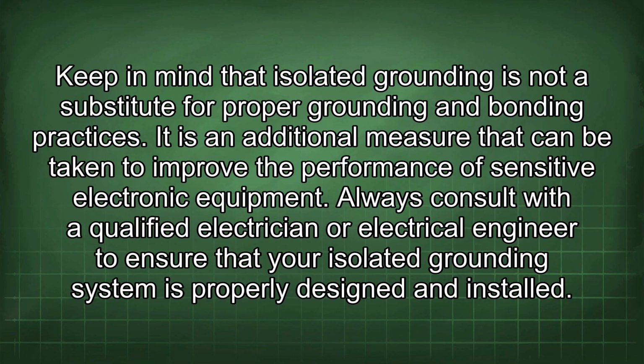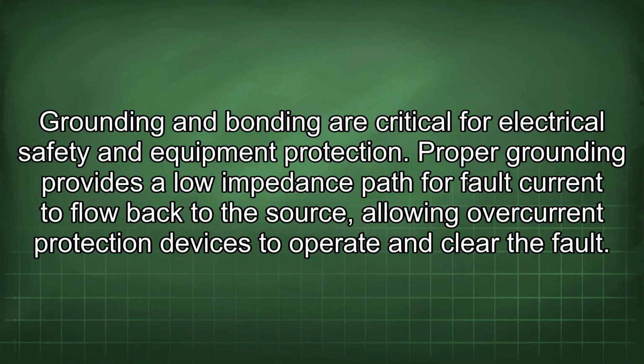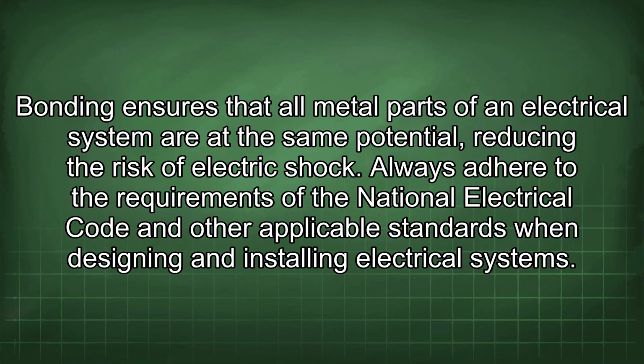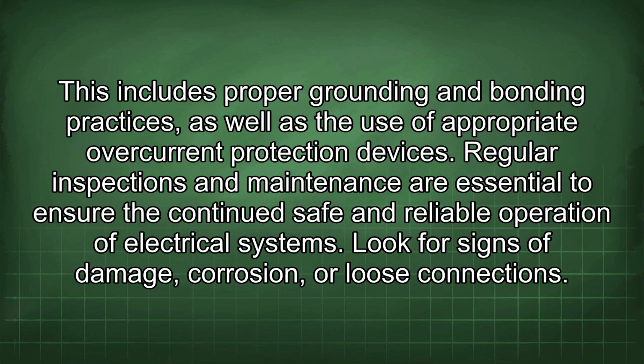Always consult with a qualified electrician or electrical engineer to ensure that your isolated grounding system is properly designed and installed. Grounding and bonding are critical for electrical safety and equipment protection. Proper grounding provides a low impedance path for fault current to flow back to the source, allowing overcurrent protection devices to operate and clear the fault. Bonding ensures that all metal parts of an electrical system are at the same potential, reducing the risk of electric shock. Always adhere to the requirements of the National Electrical Code and other applicable standards when designing and installing electrical systems. This includes proper grounding and bonding practices, as well as the use of appropriate overcurrent protection devices.